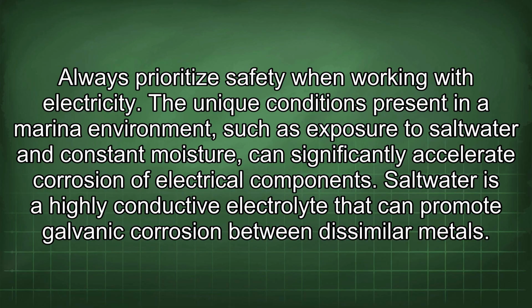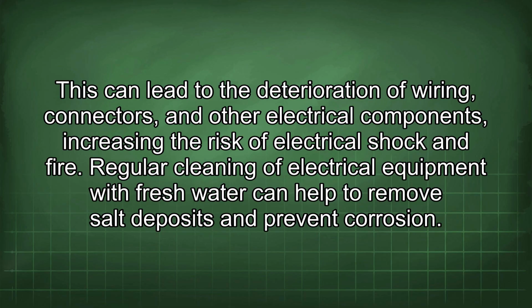The unique conditions present in a marine environment, such as exposure to salt water and constant moisture, can significantly accelerate corrosion of electrical components. Salt water is a highly conductive electrolyte that can promote galvanic corrosion between dissimilar metals. This can lead to the deterioration of wiring, connectors, and other electrical components, increasing the risk of electrical shock and fire. Regular cleaning of electrical equipment with fresh water can help to remove salt deposits and prevent corrosion.